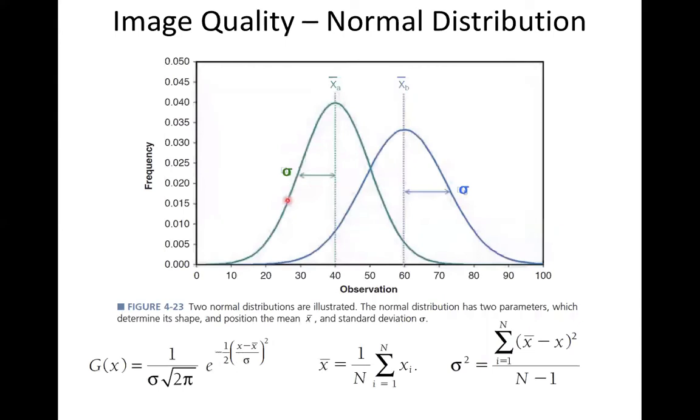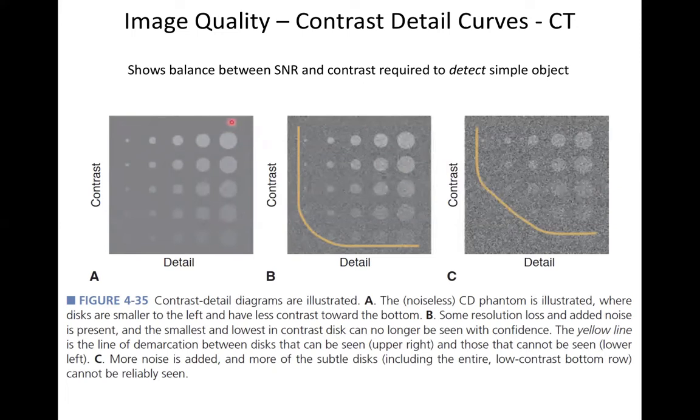Okay, so let's figure out how we characterize what we can see: that the noise in the background of this image is far less than this, which is far less than this. So how do you characterize the level of noise in the background? Not just the background, but also the level of noise inside your target. Sometimes your target gets so small, like these targets down here, that the whole target could just be noise. So what is the root mean square deviation of the pixel values inside here and outside here? That's called the noise level.